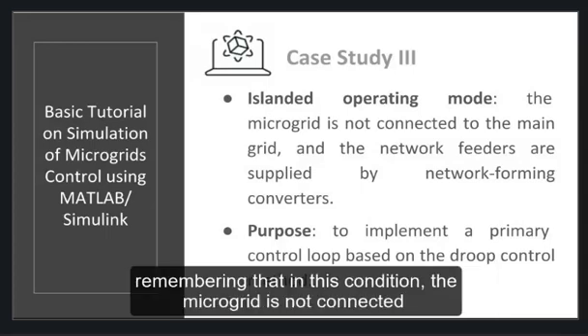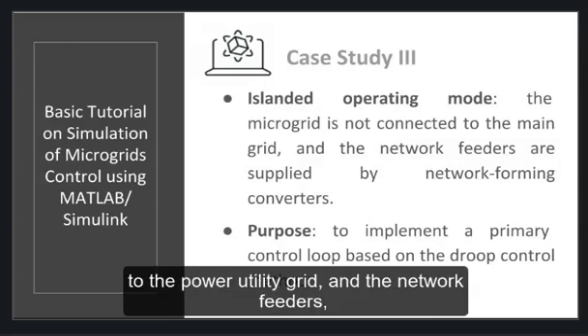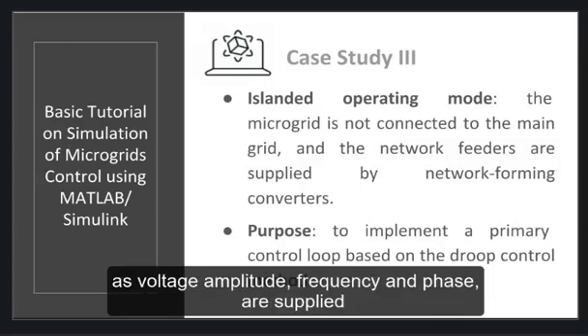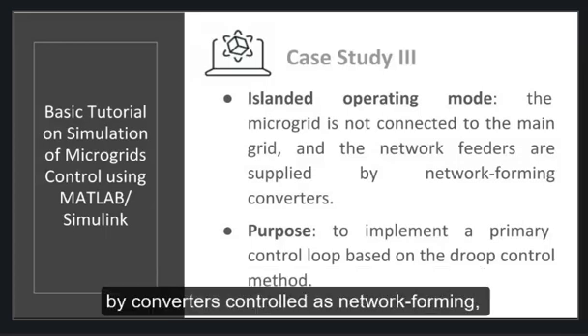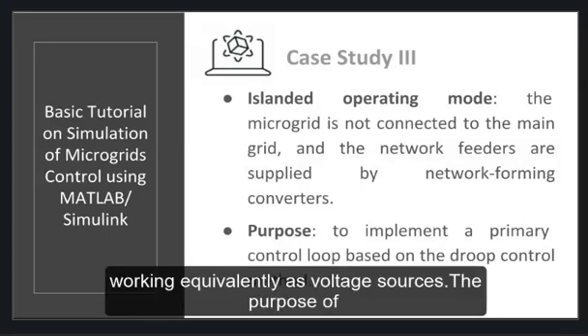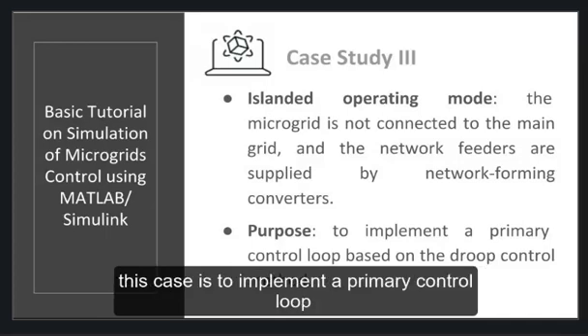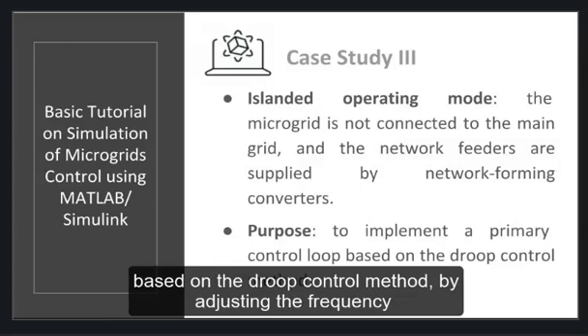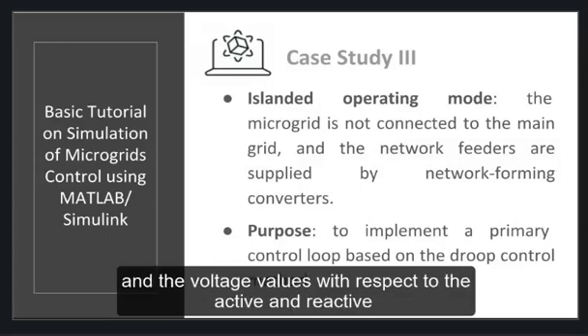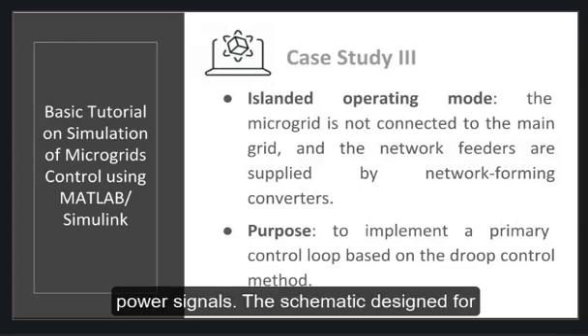Remember that in this condition the microgrid is not connected to the power utility grid and the network feeders voltage amplitude frequency and phase are supplied by the converters controlled as network forming working equivalently as voltage source. The purpose of this case is to implement a primary control loop based on the droop control method by adjusting the frequency and the voltage values with respect to the active and reactive power signals.